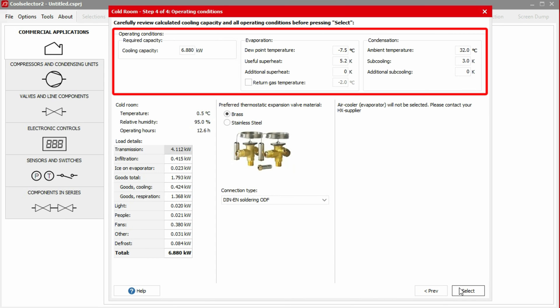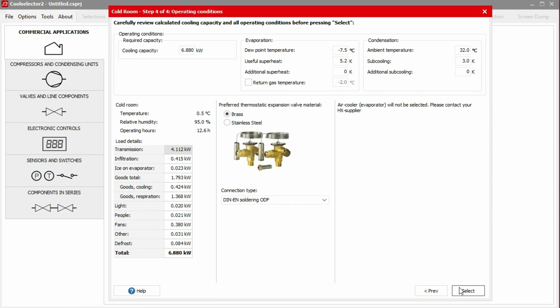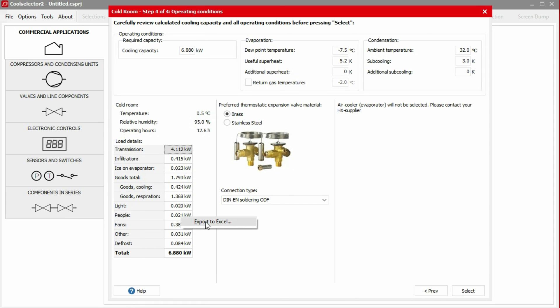In the next window, we can view the operating conditions. The suggested evaporation temperature and superheat values have been calculated for us based on the required temperature difference between the evaporator and the cold room. All values in the operating conditions can be edited if needed. The cold room heat loads are displayed on the left hand side. We can export these values by right clicking on the table and selecting export to excel.